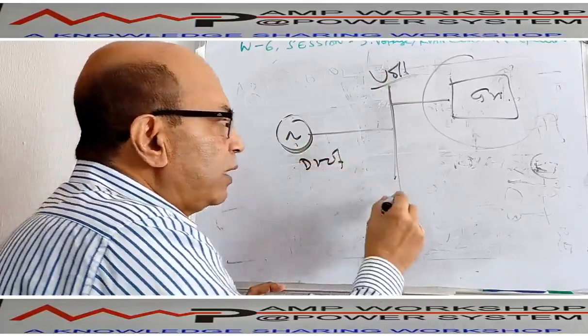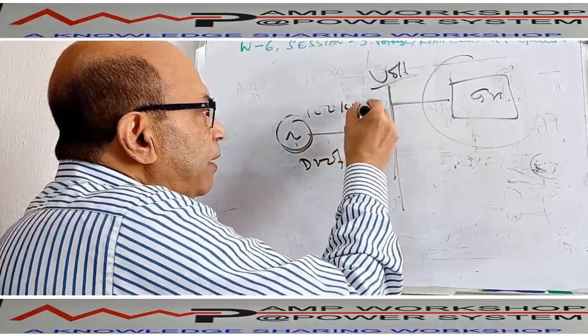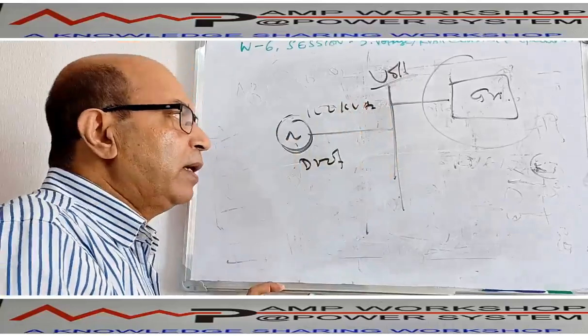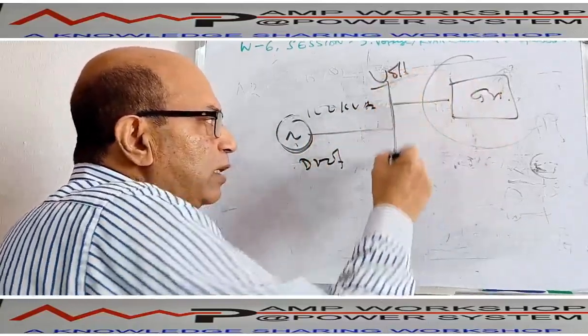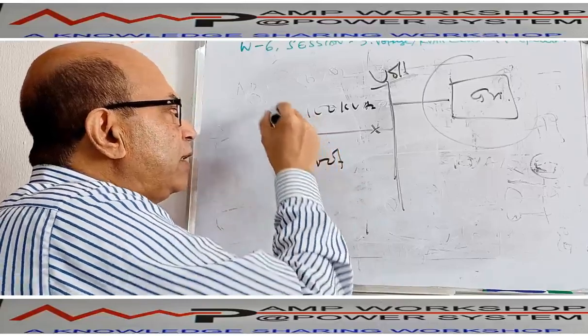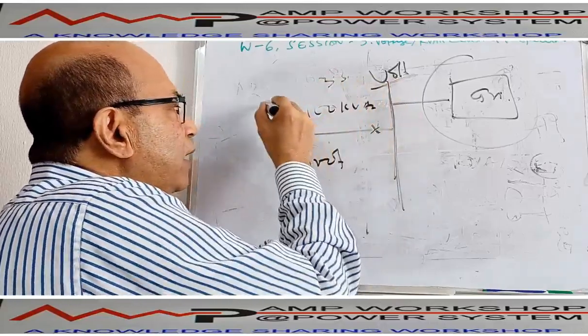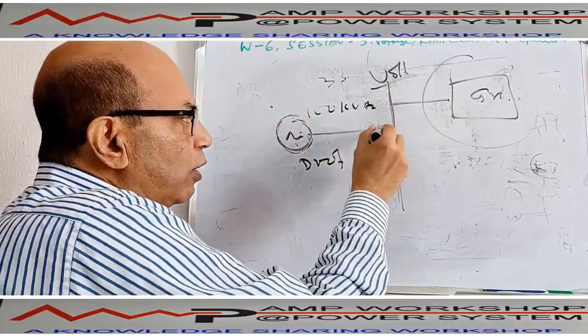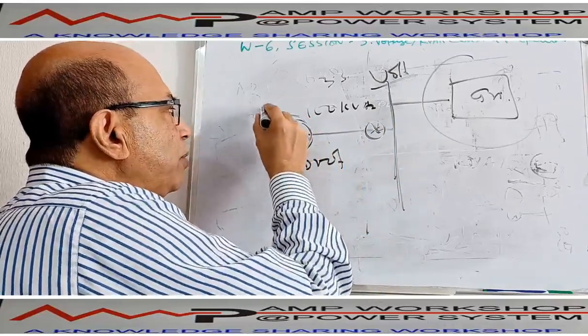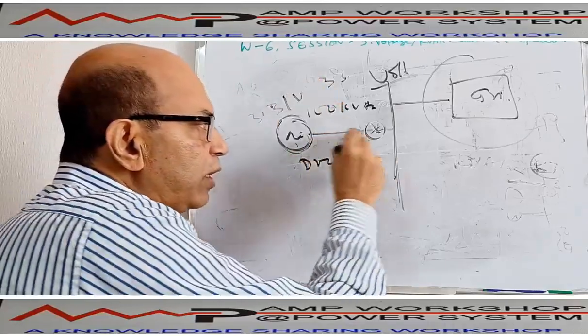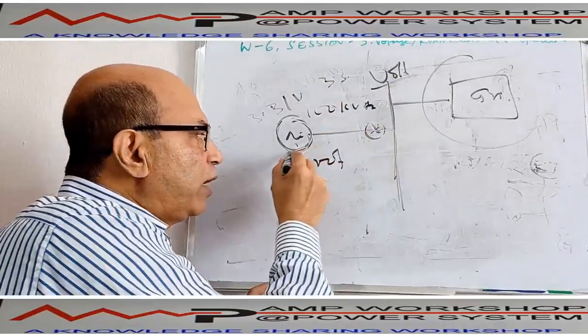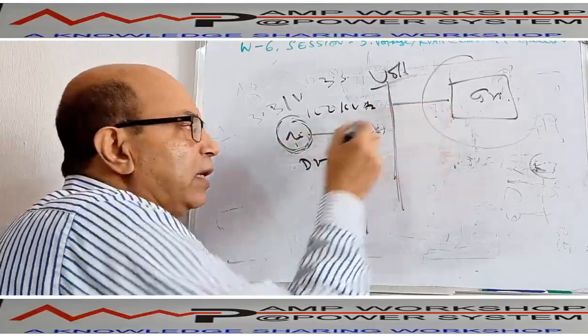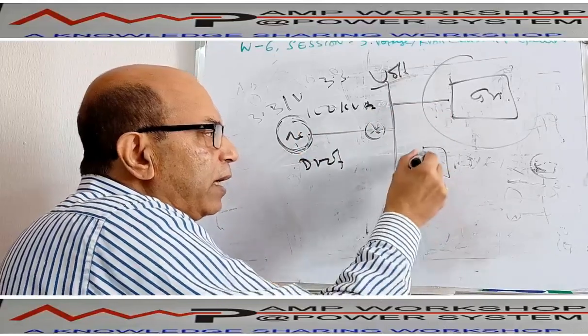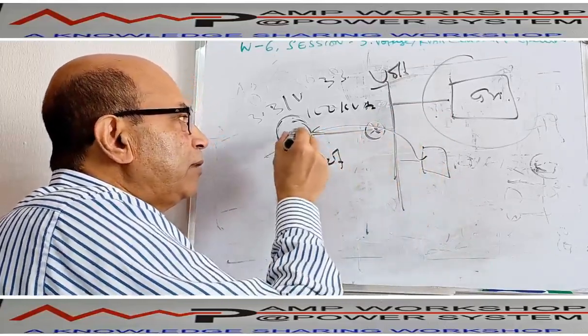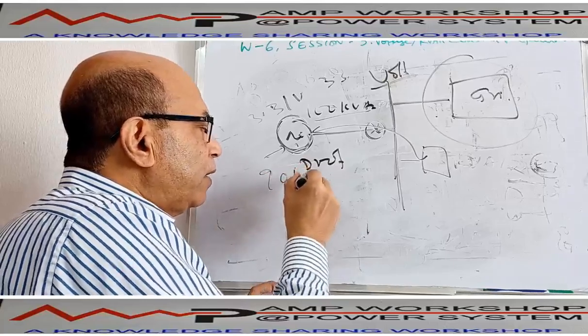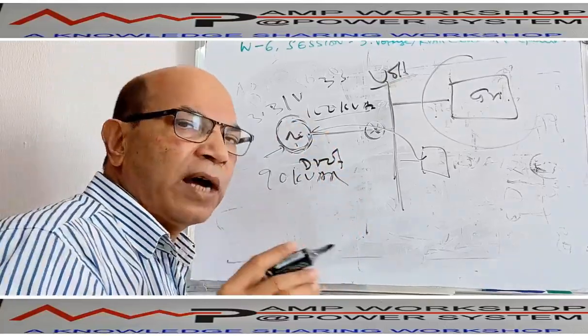Suppose this machine has a capacity of 100 kVA. You will start the machine, and the bus voltage is already there. To parallel the machine with it, you have to increase the voltage. Suppose the bus voltage is 3.3 kV; under no load condition, without closing the breaker, the machine voltage may be 3.31 kV, slightly more. Then you synchronize this machine and maintain the voltage manually, slightly higher than the bus voltage. Then automatically, whatever load you keep over here, it will take the load. Suppose this machine is 100 kVA and you load 90 kVA. The moment 90 kVA is loaded, you stop further increasing.